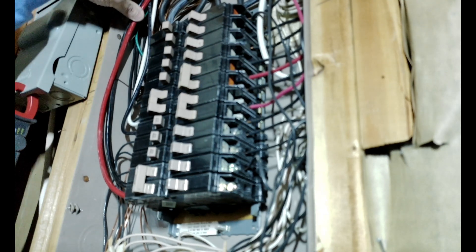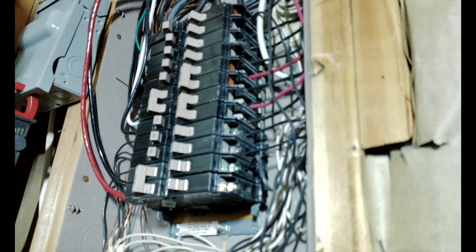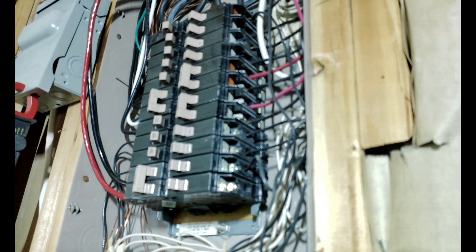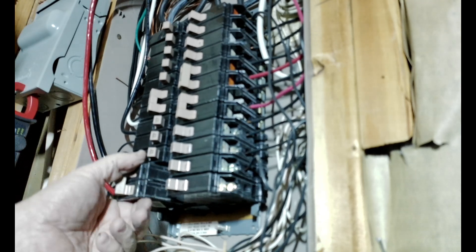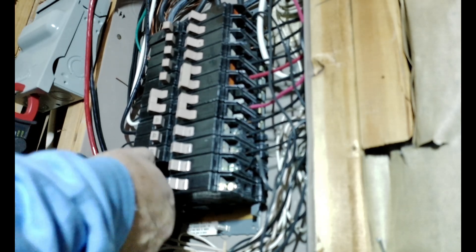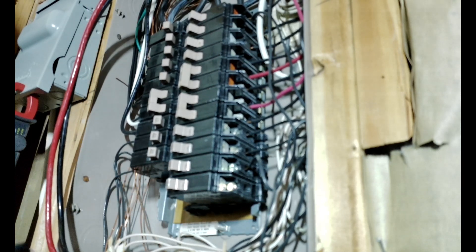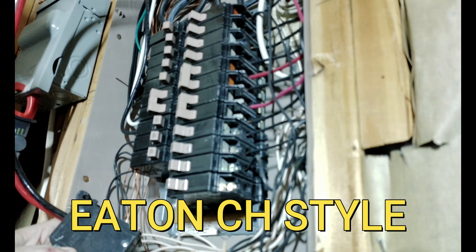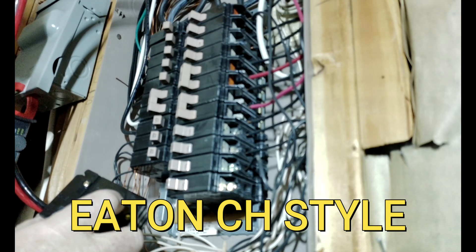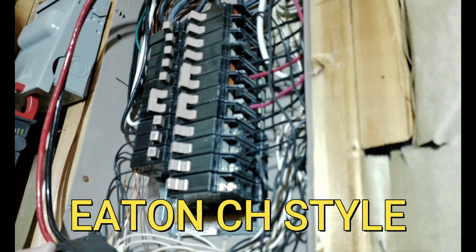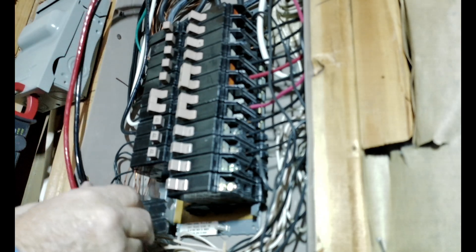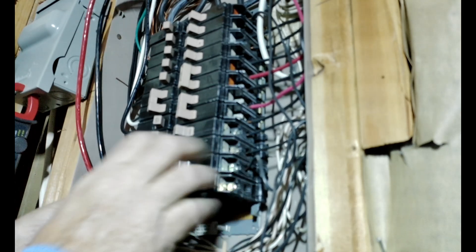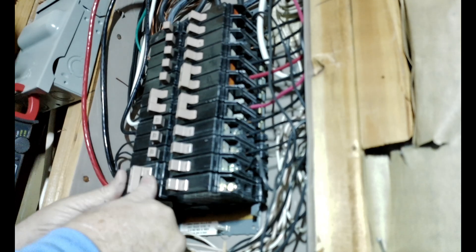Kind of bites that we can't use that breaker that I got. I've got to order a whole new one. As you can see, that wire going out to the garage will handle 60 amps. See, this one locks in this hook, whereas this one locks in the bar. This one will not work for this application, which is okay. You run into those issues when you're doing this kind of thing. So it is what it is.